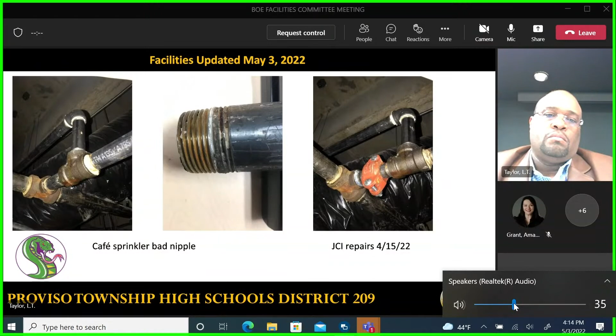Here's the nipple from the fire suppression system showing corrosion—you can see in the threads general holes that started the issue. The system was shut down and has since been repaired in collaboration with JCI, so that's all good to go. All the trouble codes have been cleared from the fire alarm system.